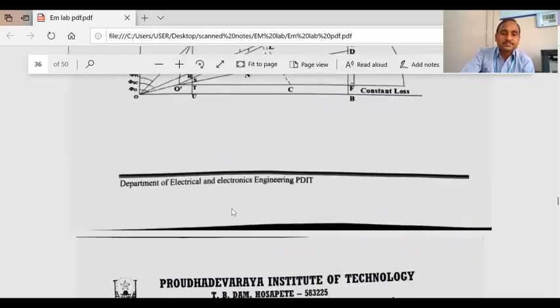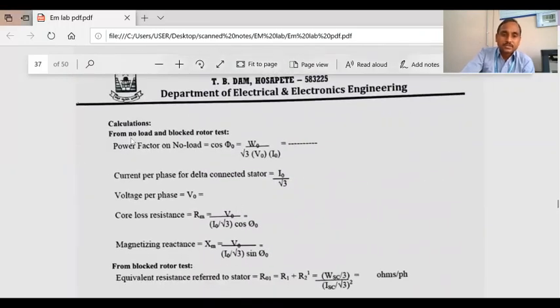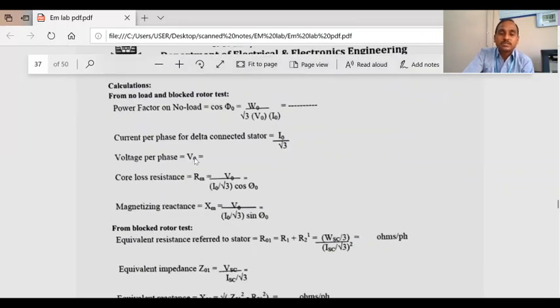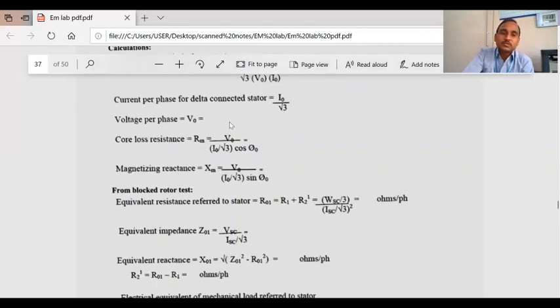Okay. After this, we need to calculate from the no load test, and from the blocked rotor test, calculations have to be done. So the power factor on no load, that is cos phi naught, is given by W naught divided by root 3 V naught into I naught. W naught, V naught, and I naught are obtained from the tabulation. And current per phase, since the stator is delta connected, is taken as the per phase value equal to the line value divided by root 3. And voltage per phase in case of delta, VL is equal to V phase. So V naught is directly taken, and that is 450 volts.